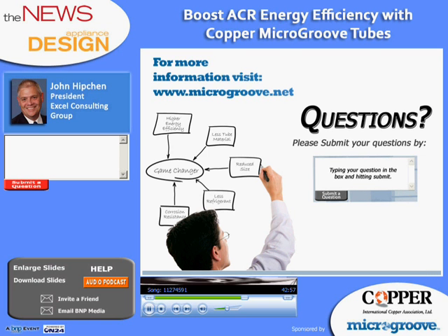Okay. One attendee would like to know, how can we manage the extra pressure drop from small tubes? Well, the extra pressure drop from small tubes, as you saw in the case studies that we showed, is best managed by redesigning the refrigerant pass. And more passes, multiple passes, help manage that refrigerant pressure loss that is typically higher with smaller diameter tubes. But as we showed several times, that pressure can easily be managed to match the pressure of the current design system.